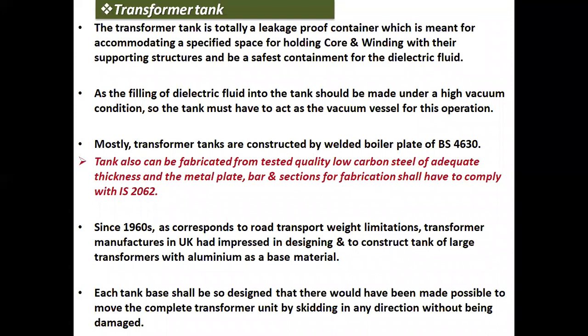Transformer tank. The transformer tank is a totally leakage-proof container meant for accommodating a specified space for holding the core and winding with their supporting structures, and to be a safe containment for the dielectric fluid. As the filling of dielectric fluid into the tank should be made under a high vacuum condition, the tank must act as the vacuum vessel for this operation.